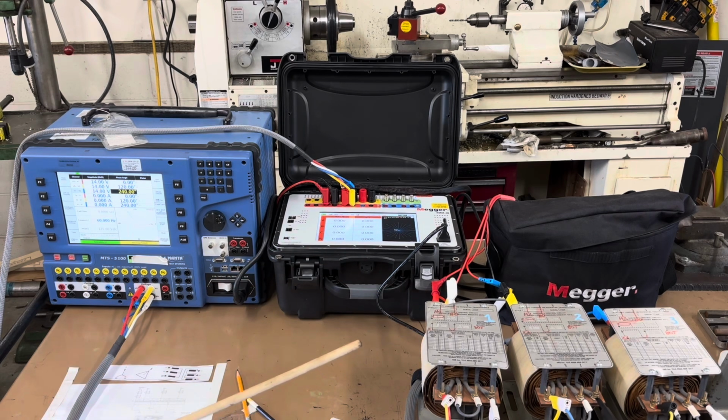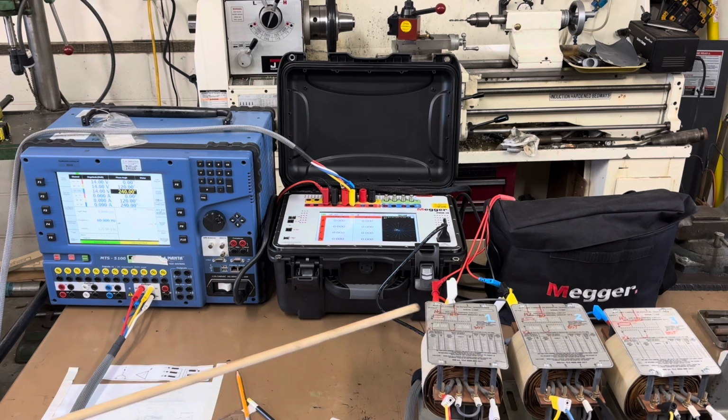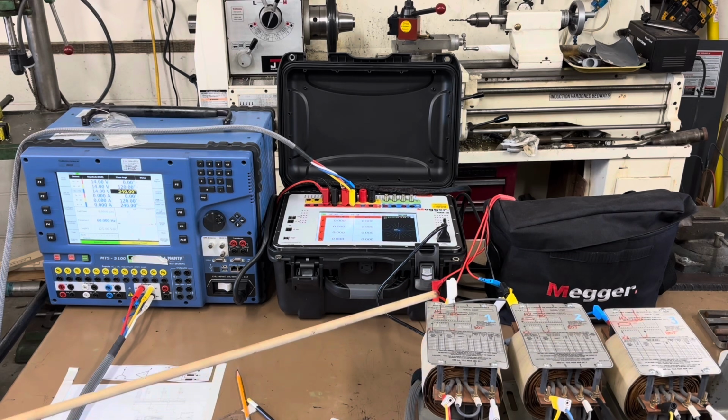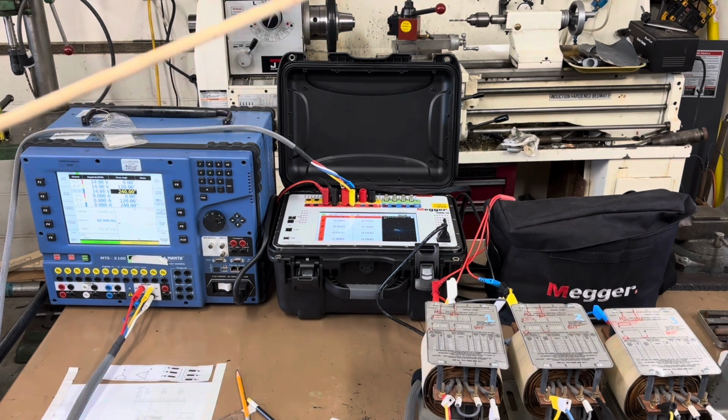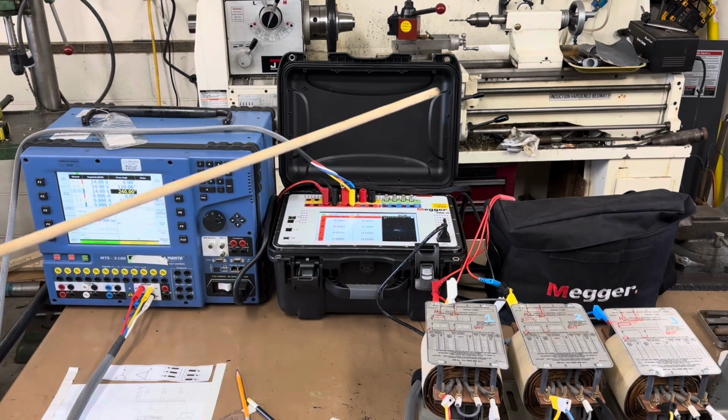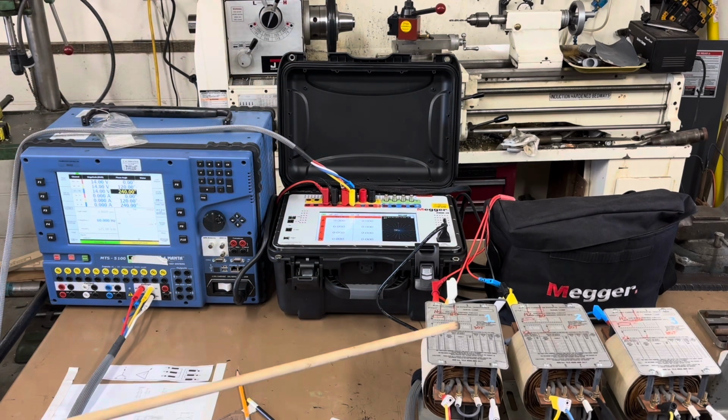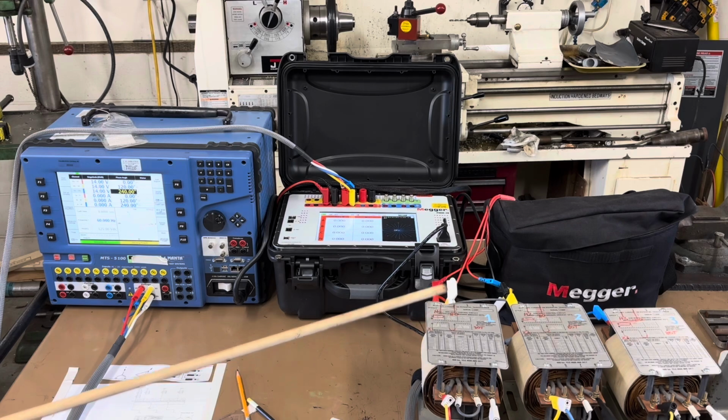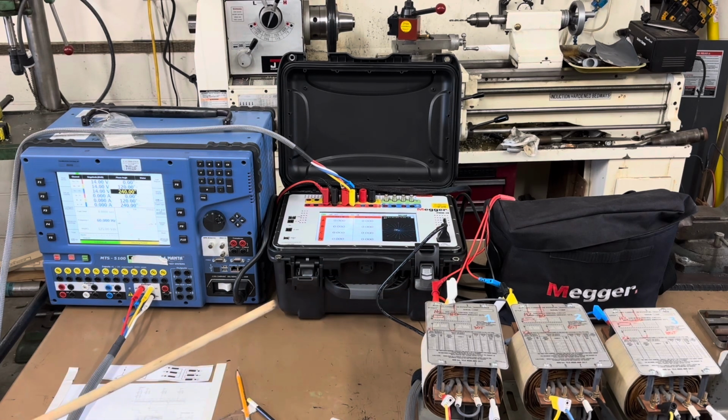and the secondary windings. We've got 3 single-phase transformers that right now are connected 160 turns on the primary, 80 turns on the secondary. At the moment, it's Y on the primary and a delta on the secondary. They are connected exactly as shown on this nameplate that we'll go over in a second. It's a YND1.